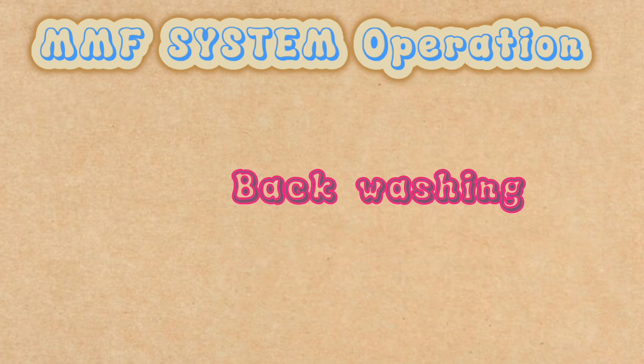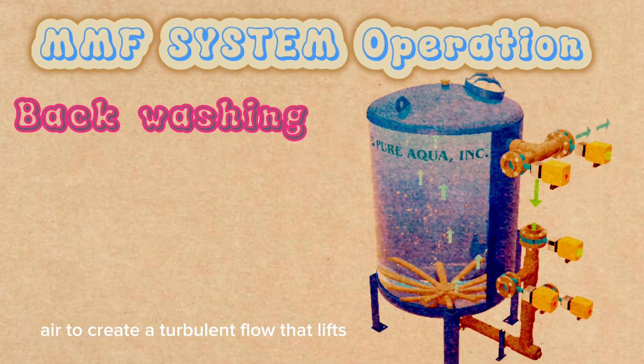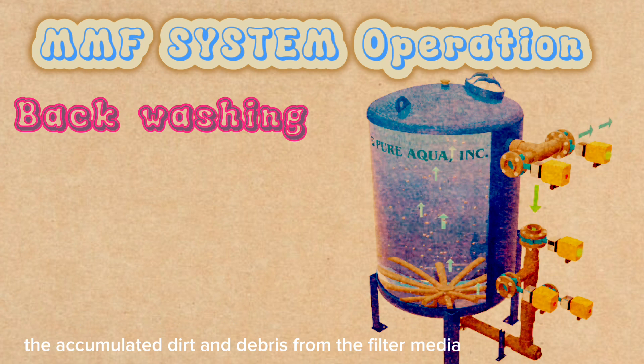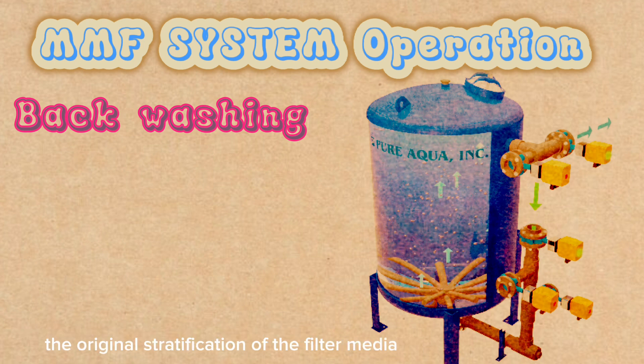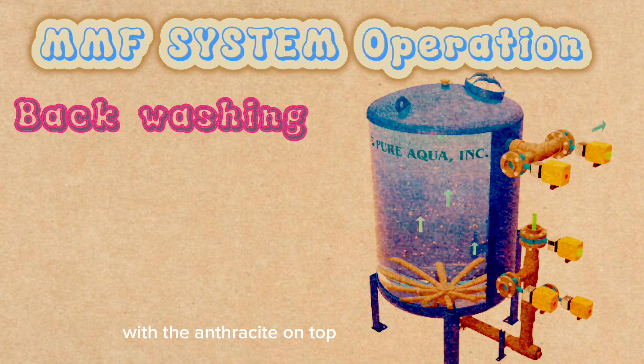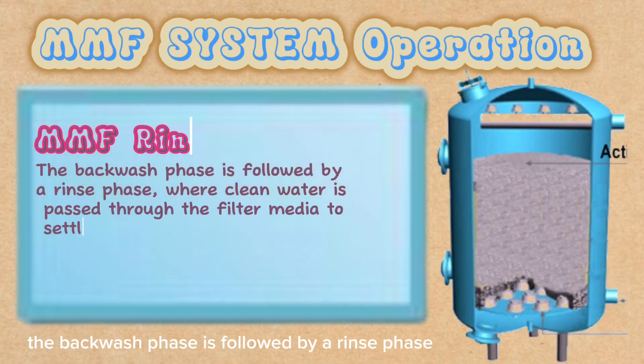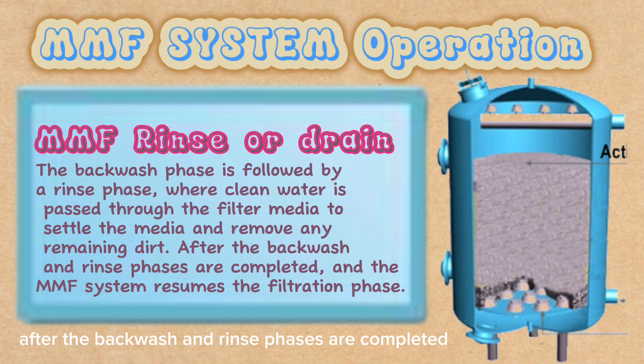During the backwash phase, the flow of water is reversed from the bottom to the top of the pressure vessel. The backwash water is mixed with air to create a turbulent flow that lifts and agitates the filter media, loosening and removing the accumulated dirt and debris and flushing them out of the pressure vessel. The backwash phase also restores the original stratification of the filter media, with the anthracite on top, the sand in the middle, and the garnet at the bottom. The backwash phase is followed by a rinse phase, where clean water is passed through the filter media to settle the media and remove any remaining dirt. After the backwash and rinse phases are completed, the MMF system resumes the filtration phase.